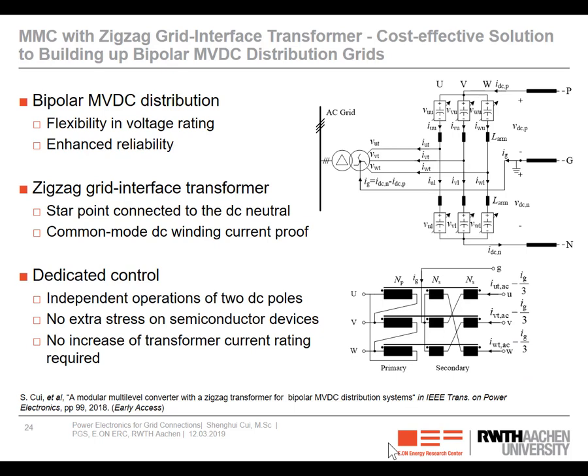And here, it's about how we can connect the medium voltage DC and the medium voltage AC in a more flexible way. When we are talking about the medium voltage distribution grid, it includes two different types: the so-called unipolar DC grid, and the bipolar DC grid. Bipolar DC distribution means that the positive pole and the negative pole on the DC side can be fully decoupled, so that we can connect our power loads either pole to ground or pole to pole. The nice thing of such a configuration is that we have flexibility in voltage rating, and also in case one pole fails, at least the other pole survives for operation.